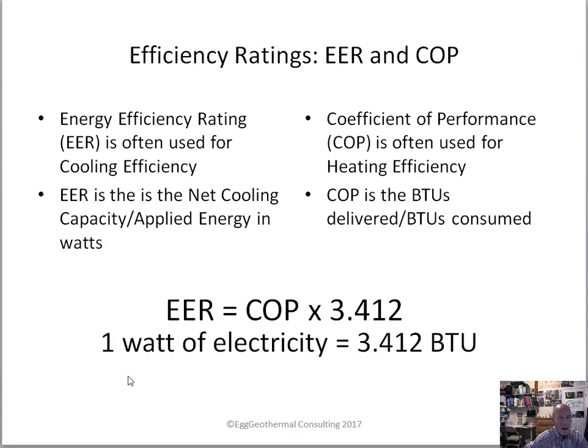Just some conversion factors: a lot of people hear the word kilowatt thrown around and they'll hear BTUs thrown around. A BTU — which is what air conditioners are regularly rated in — is a British thermal unit. This is actually the same amount of energy as burning a wooden matchstick from top to bottom, and also the same amount of energy it takes to raise one pound of water one degree Fahrenheit. One watt of electricity equals 3.4 BTUs, or 3.4 matchsticks in heat energy. You'll find heat pumps rated in EER, energy efficiency rating, and COP. Coefficient of performance works both for heating and cooling.